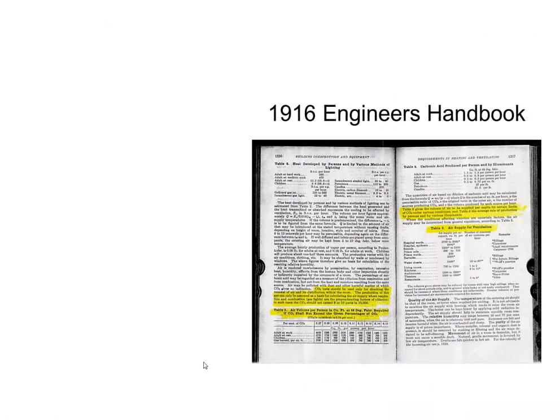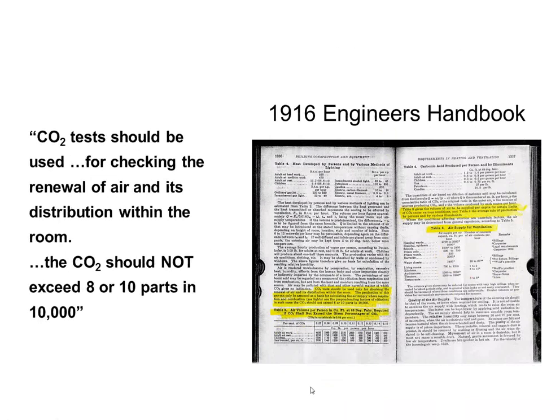All right, so CO2 is not a new idea. This has been around forever. I'm not going to read all this to you. Just know that literally it's been around forever, at least as long as all of us have been alive. The 1,000 parts per million that Chicago uses as a set point, that's not a new number either. A lot of the old documents used to say 10 parts in 10,000, which, oh, by the way, is 1,000 parts per million, same number, right? So it's been around for quite some time.